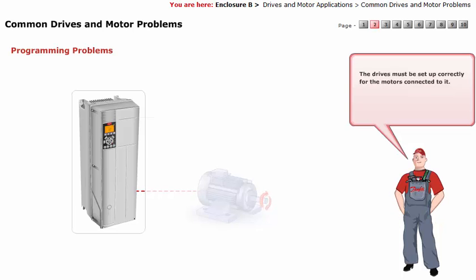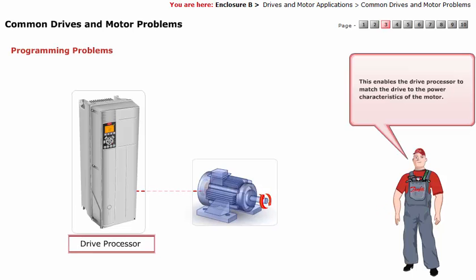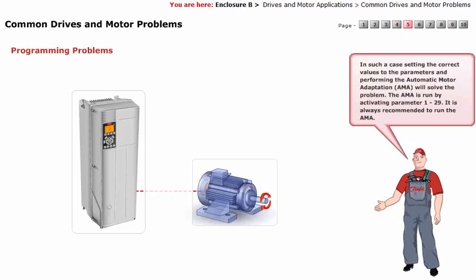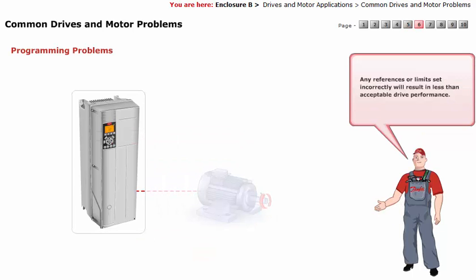The drives must be set up correctly for the motors connected to it. Parameters 1-20 to 1-25 must have the motor nameplate data entered into the drive. This enables the drive processor to match the drive to the power characteristics of the motor. The most common result of inaccurate motor data is the motor drawing a higher than normal amount of current to perform the task expected of it. In such a case, setting the correct values to the parameters and performing the Automatic Motor Adaptation (AMA) will solve the problem. The AMA is run by activating parameter 1-29. It is always recommended to run the AMA. Any references or limits set incorrectly will result in less than acceptable drive performance.